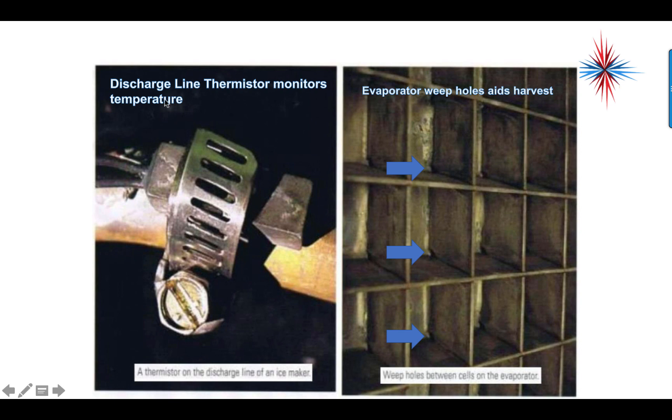The discharge line thermistor monitors the discharge temperature. That will actually, believe it or not, let us know when enough ice has built up on top of here. There's little weep holes in the back to allow water to run behind the cube as this starts going into harvest mode, because there's a little shaving of ice that will melt when that hot gas gets in here. But those weep holes allow enough water to pass through that it will actually help push the ice off and allow the ice to fall off in the harvest cycle.